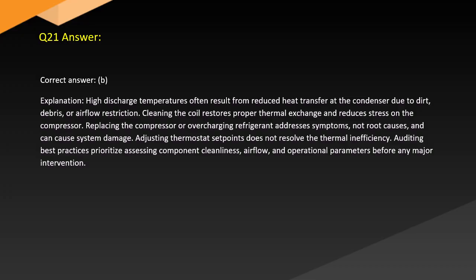Answer. Correct answer. B. Explanation. High discharge temperatures often result from reduced heat transfer of the condenser due to dirt, debris, or airflow restriction. Cleaning the coil restores proper thermal exchange and reduces stress on the compressor. Replacing the compressor or overcharging refrigerant addresses symptoms, not root causes, and can cause system damage. Adjusting thermostat set points does not resolve the thermal inefficiency. Auditing best practices prioritize assessing component cleanliness, airflow, and operational parameters before any major intervention.